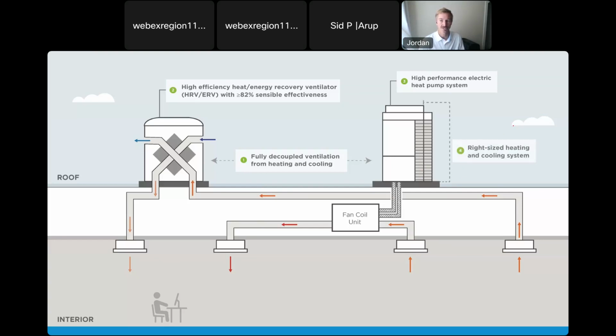And then another concept that we find oftentimes gets ignored or purposely overlooked in commercial applications is right sizing the heating and cooling system. So using load calculations that correctly deduct the amount of ventilation load that's been eliminated by a passive heat recovery, energy recovery ventilator, and without significantly using safety factors, and using good diversity and correct assumptions. We found time and time again that systems are oftentimes installed with far more capacity than they need to be. And this not only costs more for equipment, it's more expensive to maintain, and it usually operates significantly less efficiently when it's oversized.